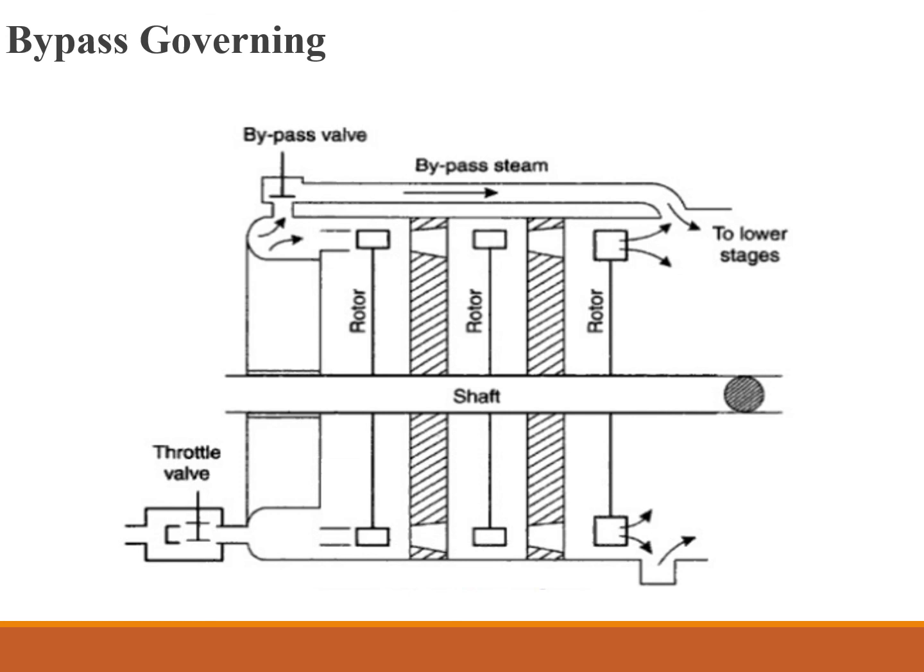The steam entering the turbine passes through the inlet valve, which is controlled by the governor. The steam after passing through the inlet valve enters the nozzle box or steam chest. For loads up to the economical load, the governing is effected by throttling, that is, by controlling the load.